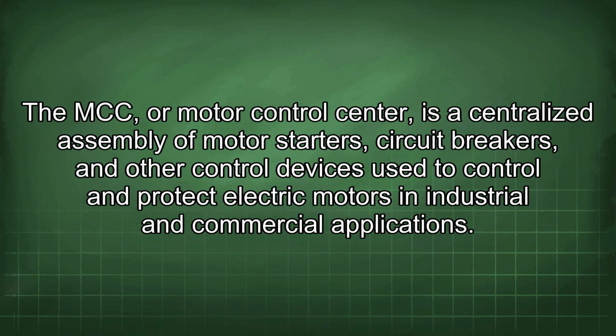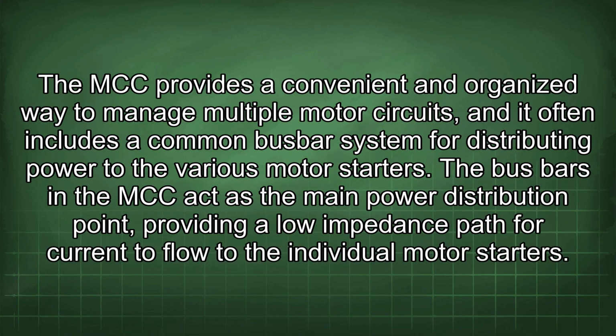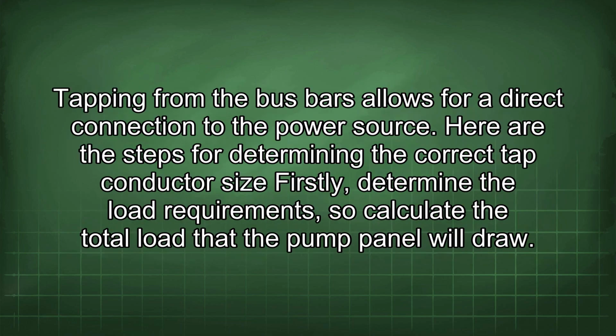The MCC, or Motor Control Center, is a centralized assembly of motor starters, circuit breakers, and other control devices used to control and protect electric motors in industrial and commercial applications. The MCC provides a convenient and organized way to manage multiple motor circuits, and it often includes a common busbar system for distributing power to the various motor starters. The bus bars in the MCC act as the main power distribution point, providing a low impedance path for current to flow to the individual motor starters. Tapping from the bus bars allows for a direct connection to the power source.